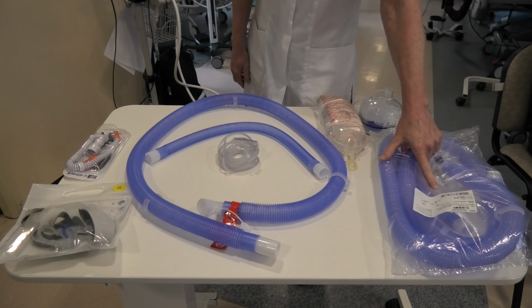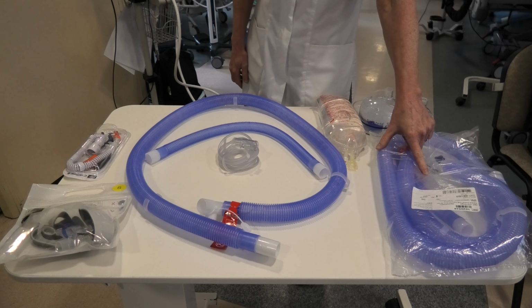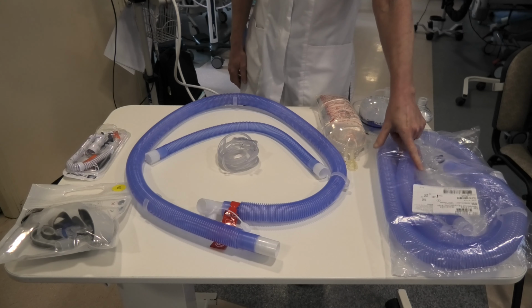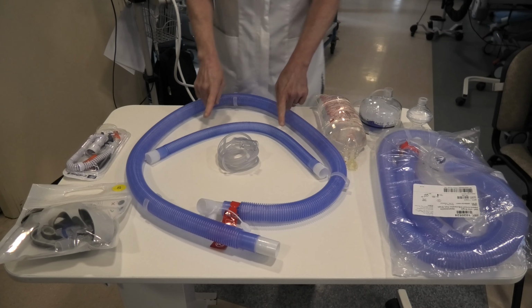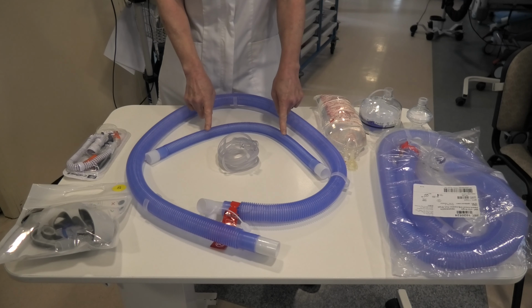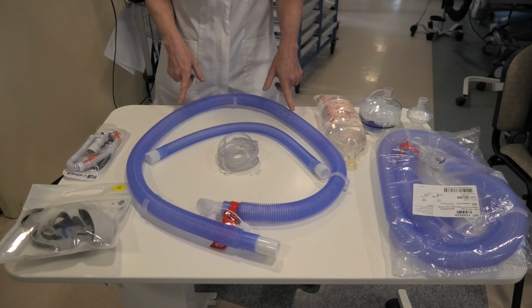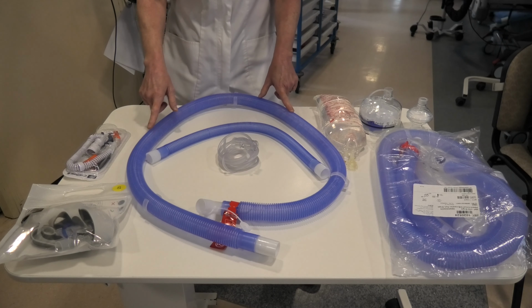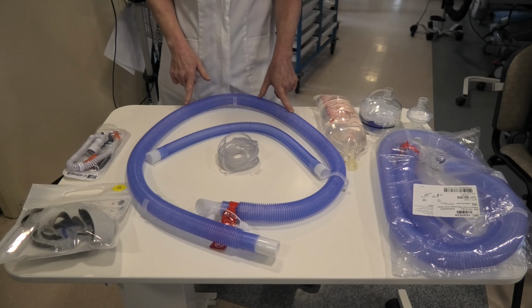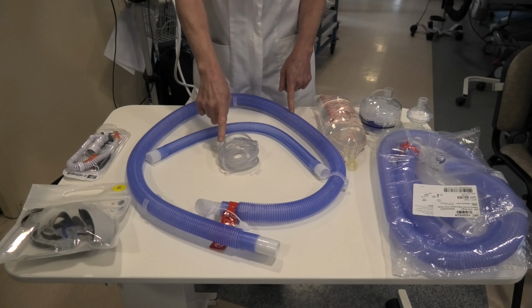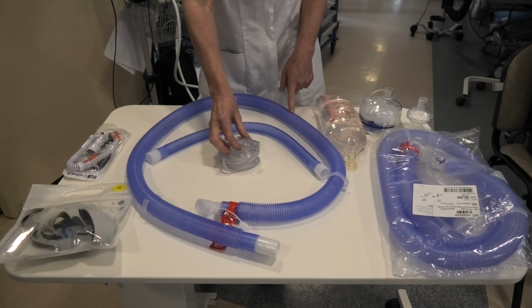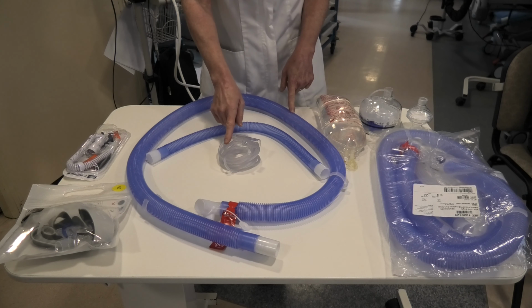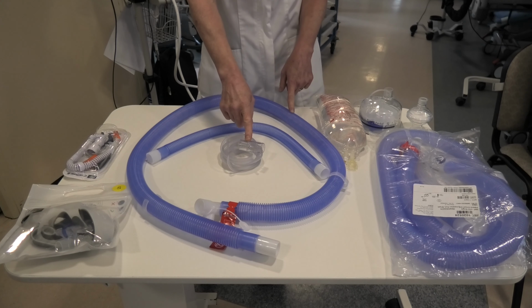This is a wet circuit that we use for nasal high flow and sometimes for CPAP. Within this bag, we've got short tubing that goes from the ventilator to the humidifier. We've got long tubing which goes from the humidifier to the patient. This has got a heater wire inside it so it stops rain out in the tube. The other thing we've got is a pressure line and an exhalation port. We only use the pressure line and the exhalation port if we're using CPAP.